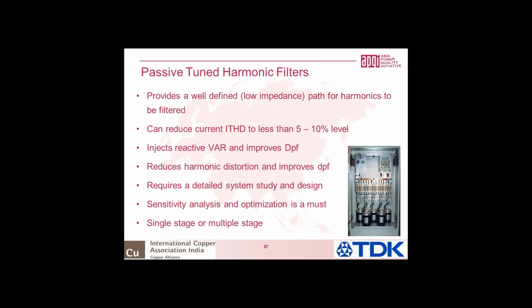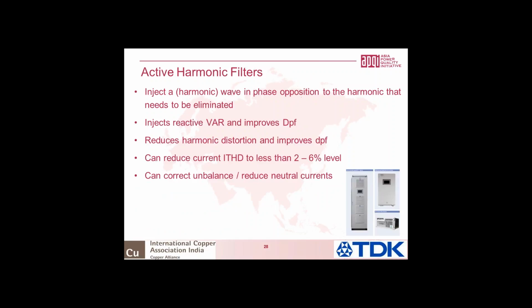Then it brings us to the next solution, which is active harmonic filters. They inject synthesized harmonics which are in phase opposition to the system harmonics, by which there is an active cancellation. They can, of course, inject fundamental capacitive VAR. That means they can improve the displacement power factor as well as the distortion power factor. They can reduce the current distortion to a level of 2 to 6%. And another advantage with active filters is, apart from giving capacitive VAR compensation as well as harmonic filtering, they can also correct for unbalance in load currents, and they can reduce neutral currents.